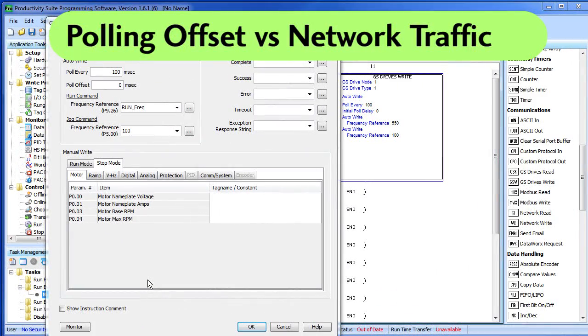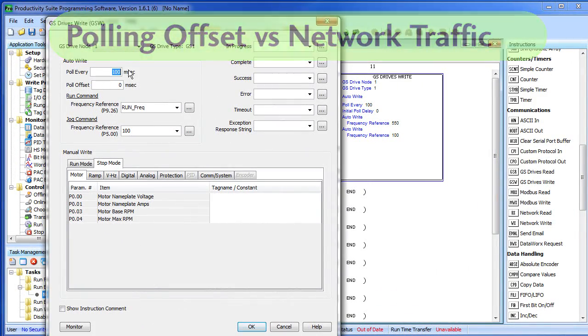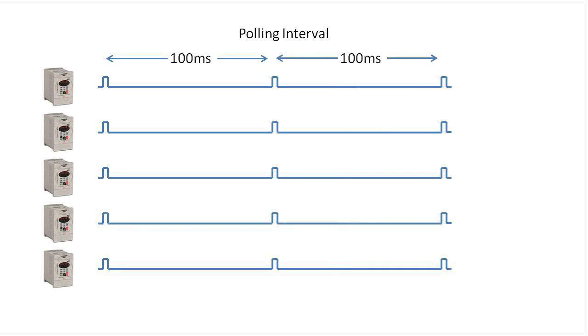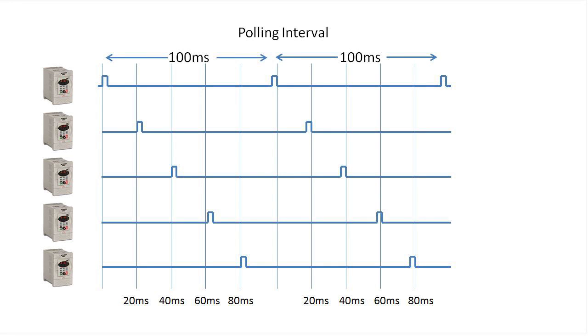You set the rate at which drives get updates while the GS drive read or write is active here. This polling offset allows you to space out communications to different drives to help improve the performance and minimize congestion on the network. For example, suppose we have 5 drives and we are polling them every 100 milliseconds.